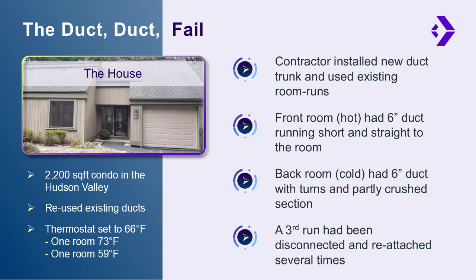This 2,200 square foot condo in the Hudson Valley reused existing ducts from a prior natural gas furnace. But the homeowner complained about room temperatures. With the thermostat set to 66 degrees Fahrenheit, one room was too hot at 73 degrees Fahrenheit, while the other was too cold at 59 degrees Fahrenheit. So what's the issue? The signed contract required furnishing and installing new insulated ductwork, but the contractor only installed a new duct trunk and reconnected the existing room runs.